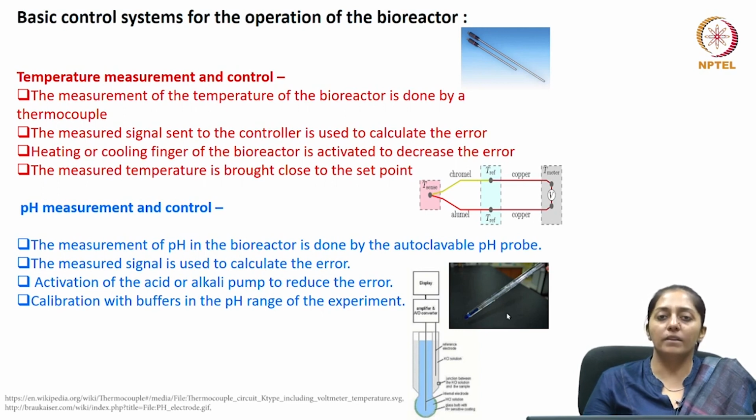Depending on this error between the set point and the current temperature of the broth, water from the chilling unit is circulated through the heating or cooling jacket, or the heating element or the cooling element is switched on or off accordingly. This happens until the measured temperature is brought close to the set point.